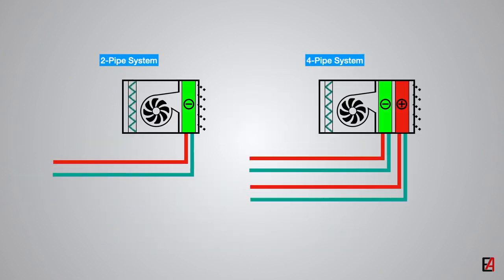Next one is the four-pipe system, where two pipes are for chilled water supply and return and two pipes are for hot water supply and return, which can be used for both cooling and heating applications without affecting each other.